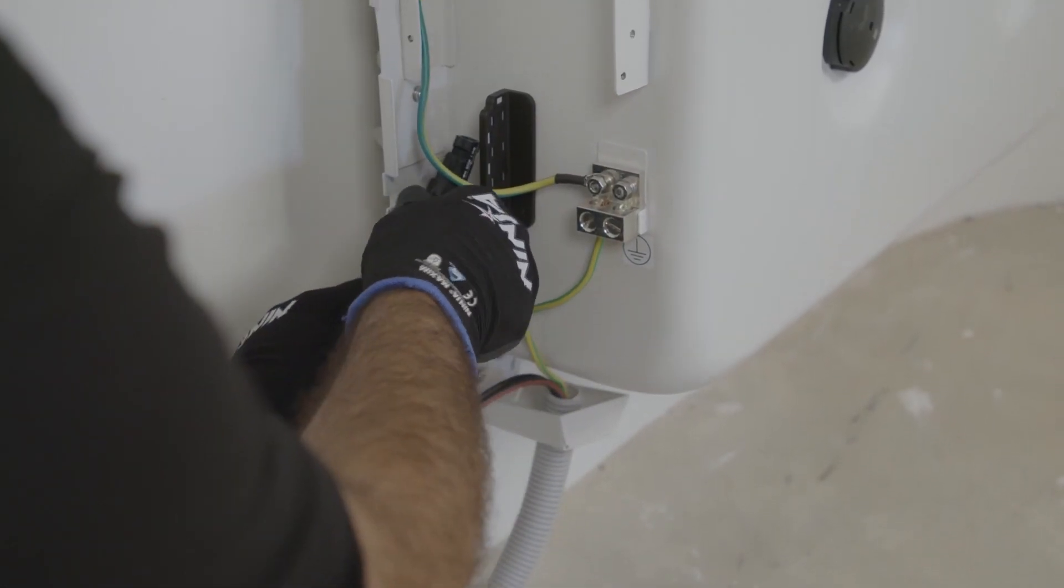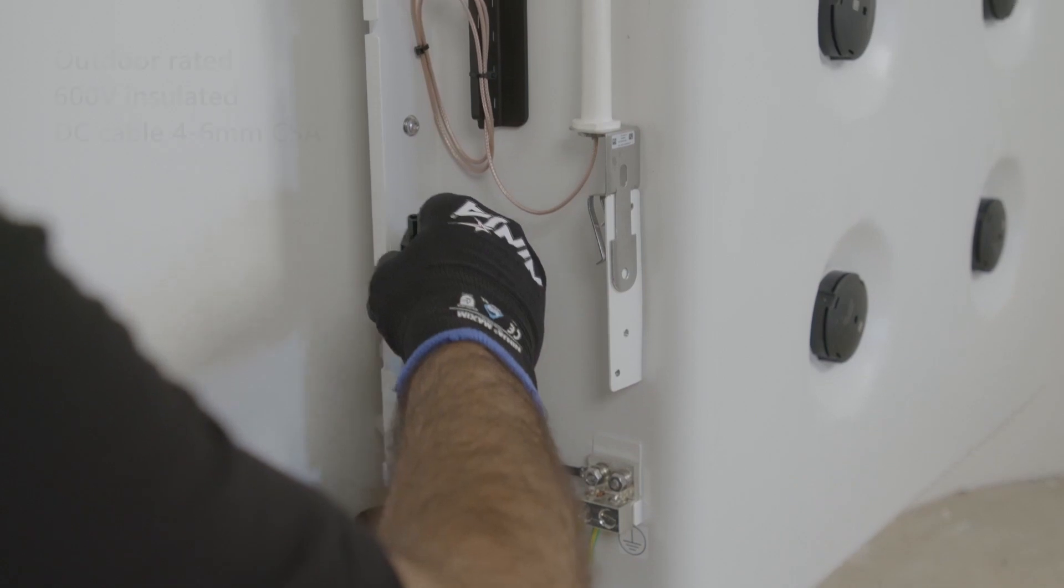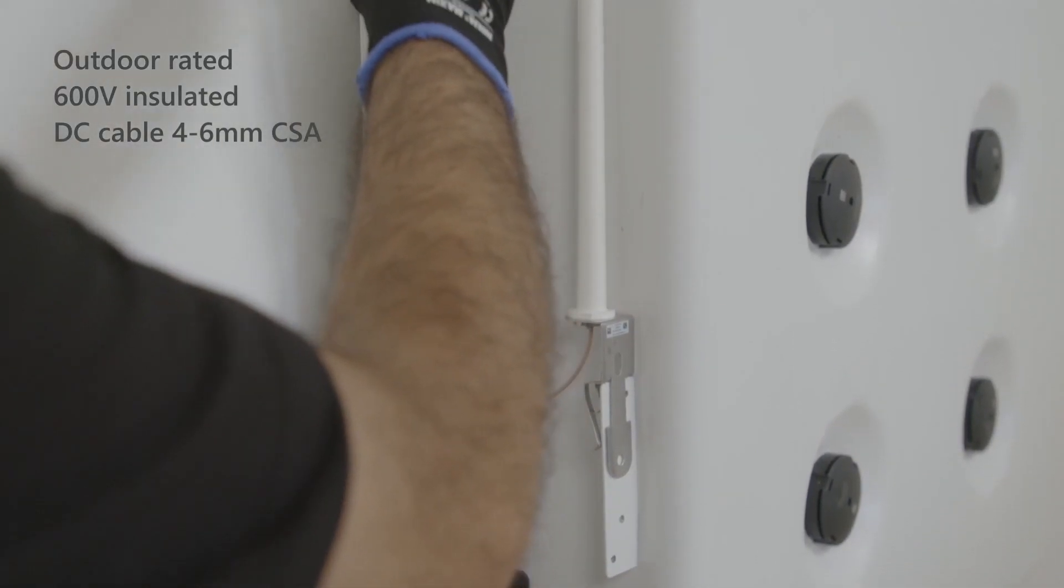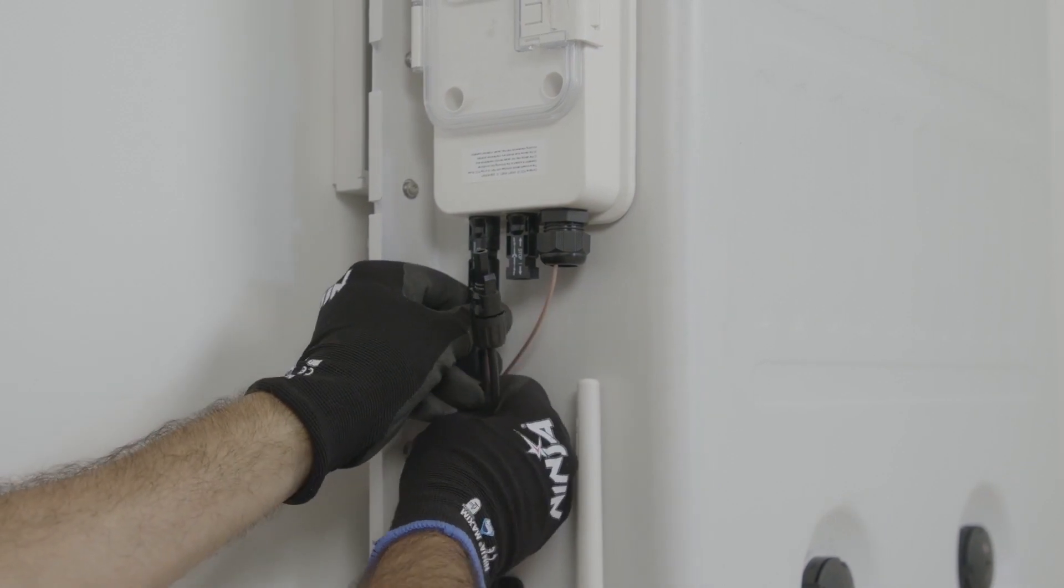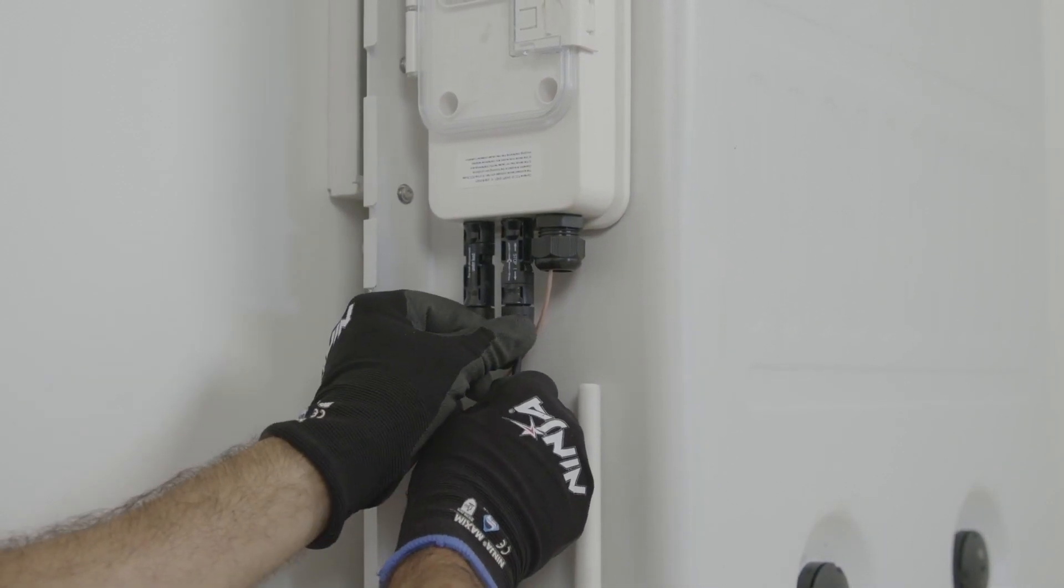Once the earth is in we can then fix the DC. With the battery comes supplied two MC4 connections, so simply connect those to suitable PVDC 600 volt rated cable and connect them into the positive and negative associated terminals.